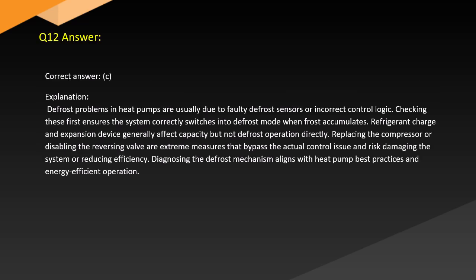Answer. Correct answer: C. Explanation. Defrost problems in heat pumps are usually due to faulty defrost sensors or incorrect control logic. Checking these first ensures the system correctly switches into defrost mode when frost accumulates. Refrigerant charge and expansion device generally affect capacity but not defrost operation directly.